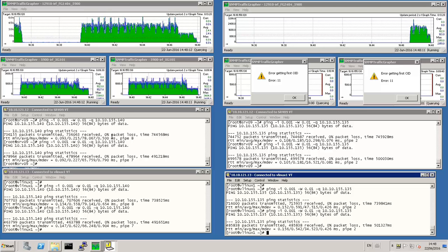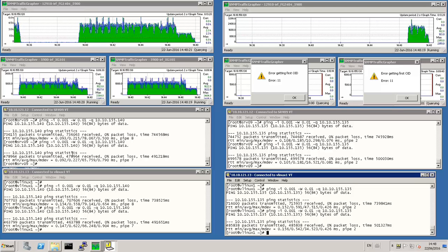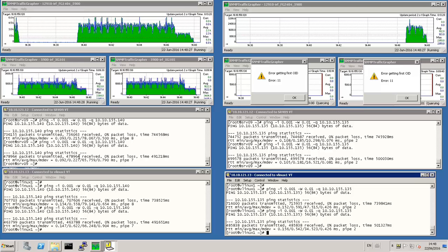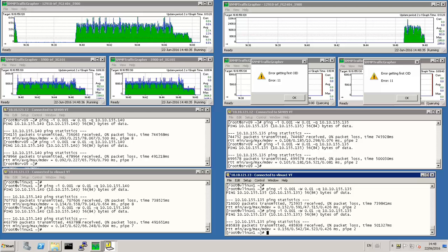So overall, if we cumulate the total impact of upgrading unit 1 first and then unit 2, we have, as I said before, 92 packets lost on this first drop, and then on the following one 11 packets, which is a total of 103 packets, so a bit more than 1 second.